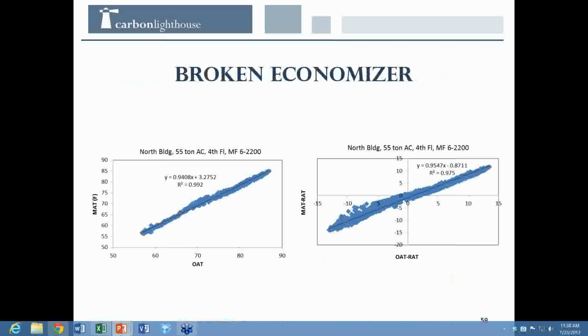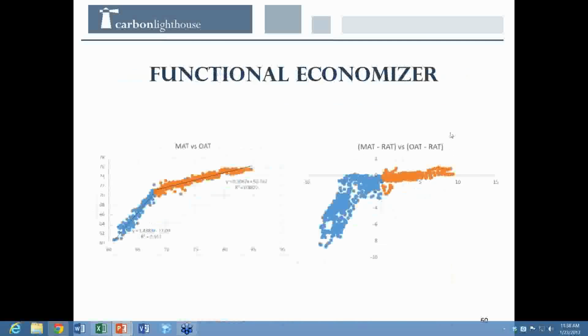This indicates that your economizer is letting in about 95% outside air all the time. In other words, it's not recycling air from inside the building. So if it's a pleasant 60 degrees outside, that's wonderful, but if it's 100 degrees or 20 degrees, you're spending an awful lot of time and energy conditioning air. Now, what your mixed air temperature should show you is this.